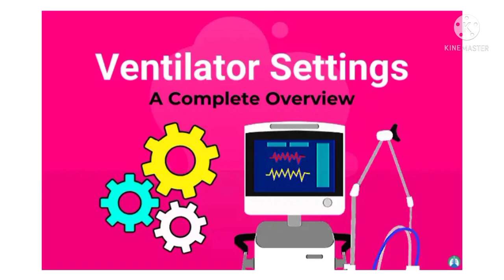High pressure limit regulates the maximum pressure the ventilator can generate to deliver the VT. When the pressure limit is reached, the ventilator terminates the breath and spills the undelivered volume into the atmosphere. Usual setting, 10 to 20 cm H2O above peak inspiratory pressure.